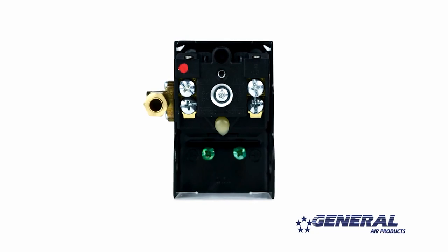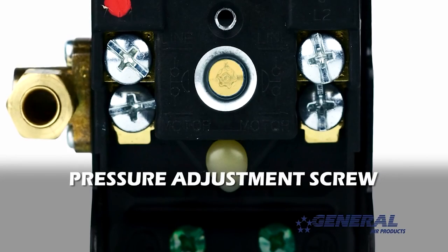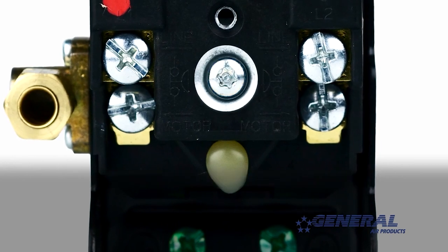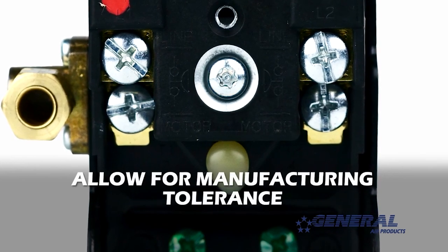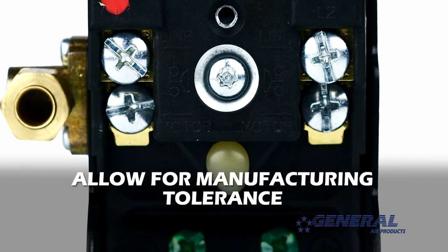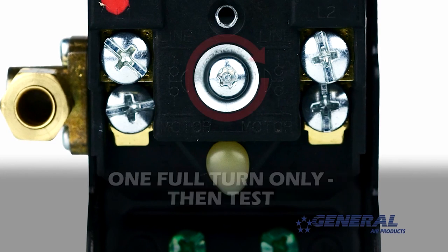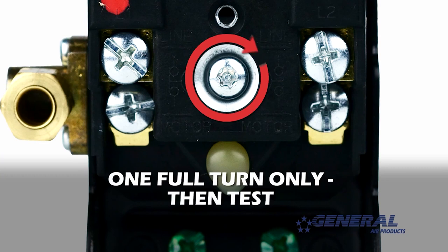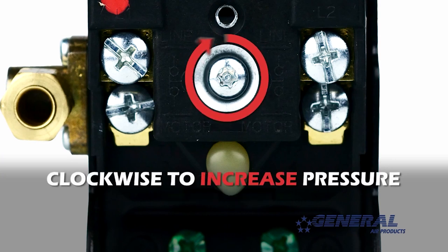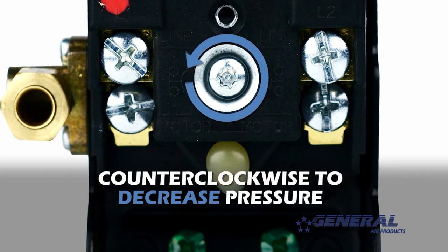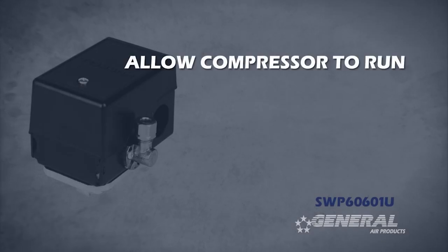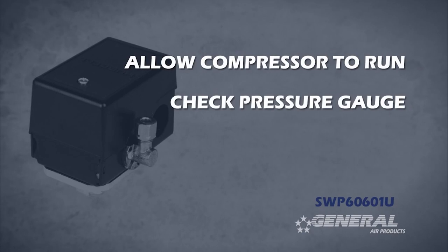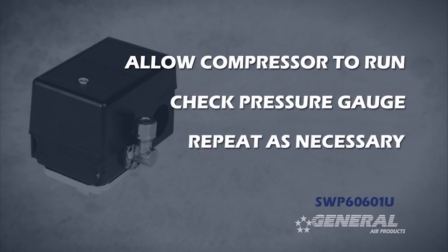to speak with a tech for further instruction. To adjust the cut-in and cut-out pressure simultaneously, you need to turn the pressure adjustment screw on the pressure switch. Now remember, adjusting the pressure switch is not an exact science. Some manufacturing tolerance should be allowed for. Start by turning the pressure adjustment screw one full turn only, clockwise to increase pressure, counterclockwise to decrease pressure. Once you've made one full turn, let the compressor run. Check the closest pressure gauge to see where the pressure lands. Simply repeat this process until you reach the desired pressure setting.